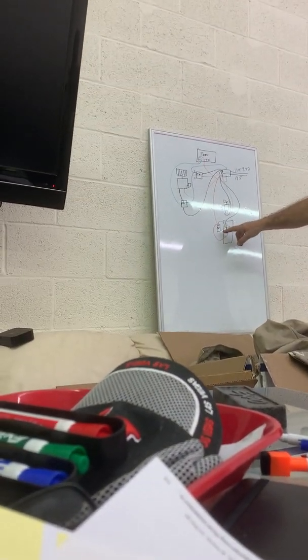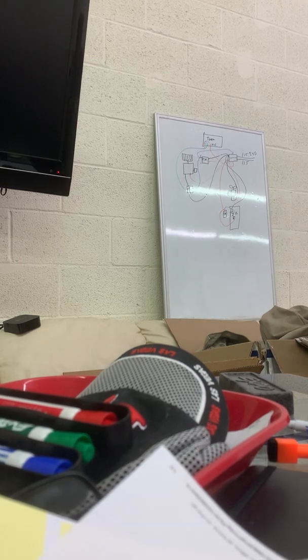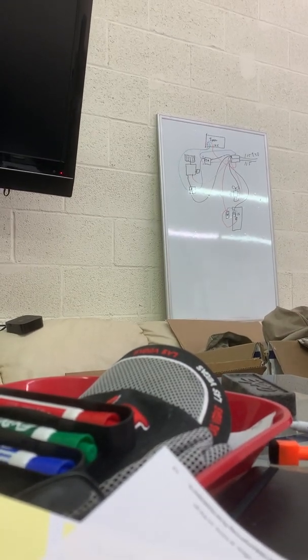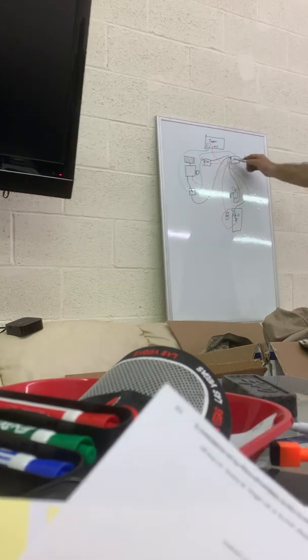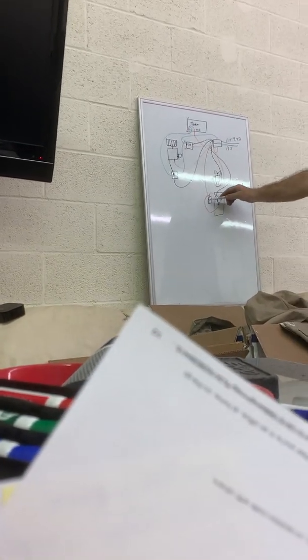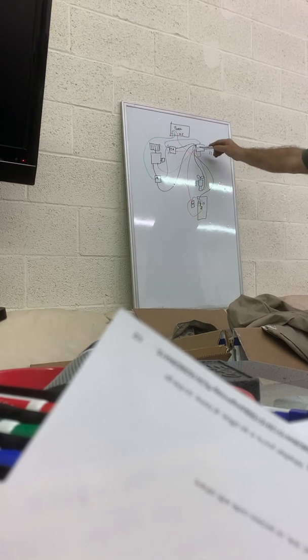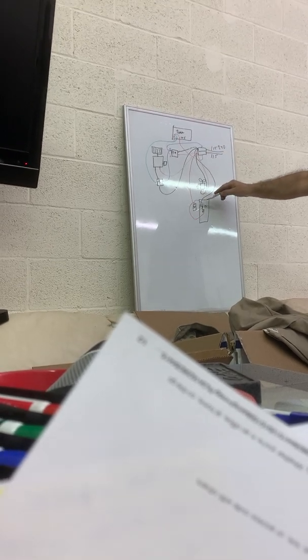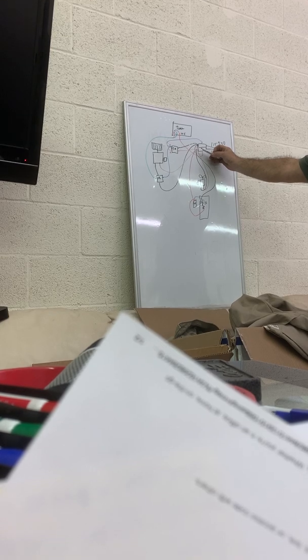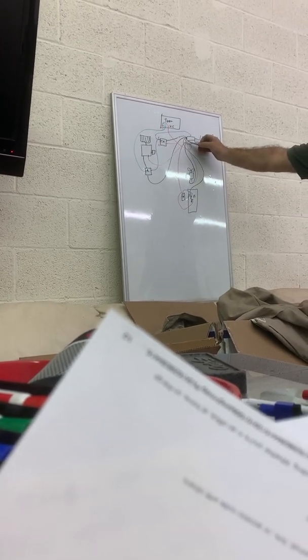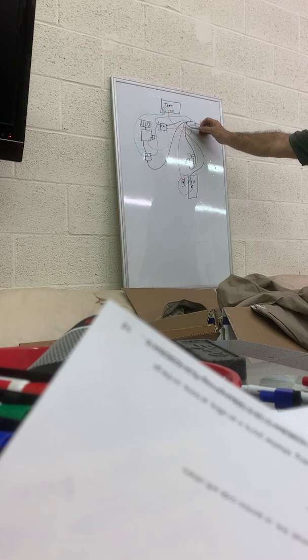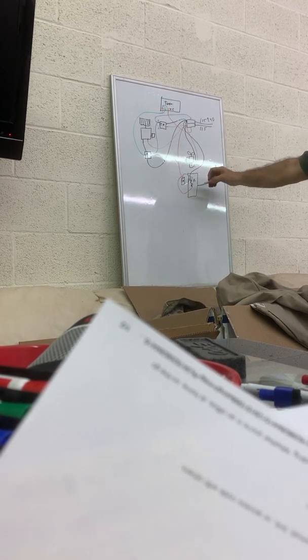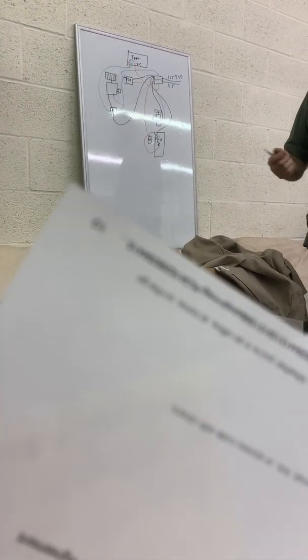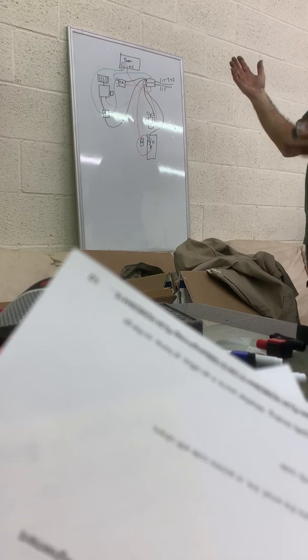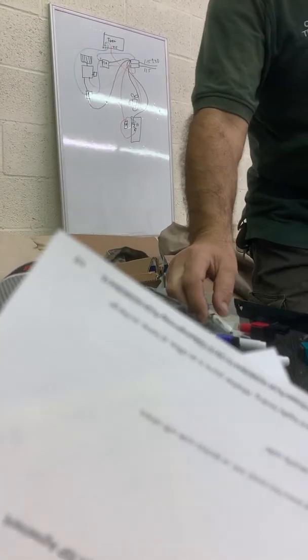Let's say the compressor can be wired differently - not this compressor wire, it's not going to go this way. Let's say it goes through the capacitor, or it might go straight. The two wires can distribute straight from here, one here, one there, not through the capacitor. It's just a variety of setups you have to see in the field. There's different varieties for everything.